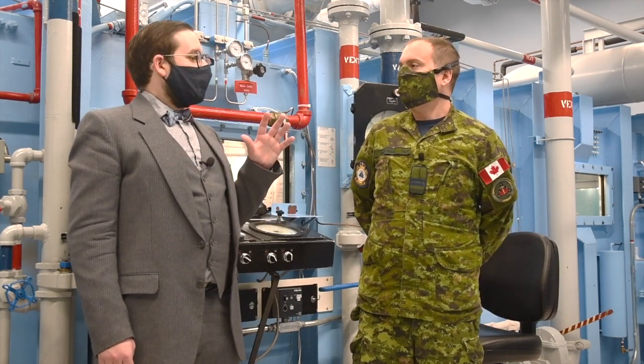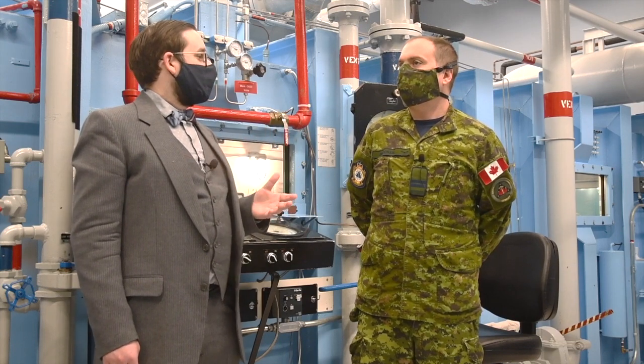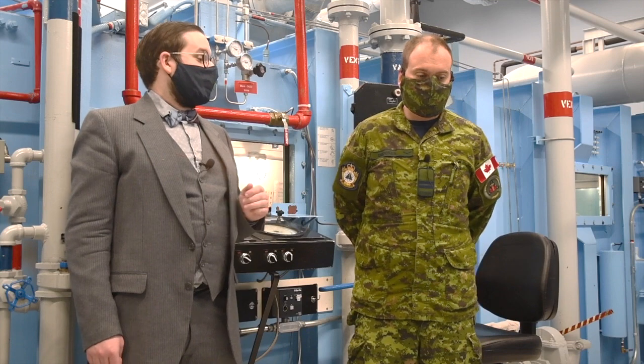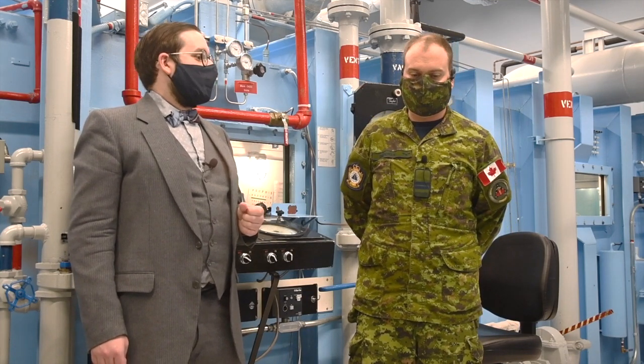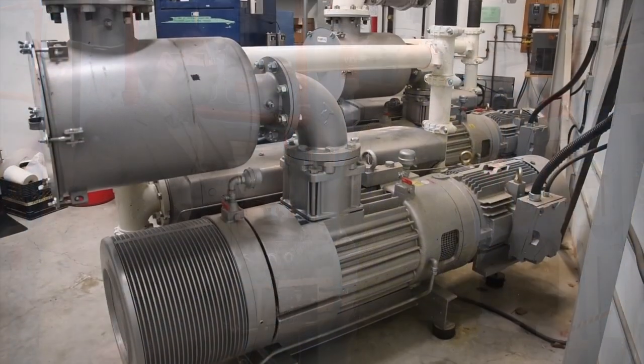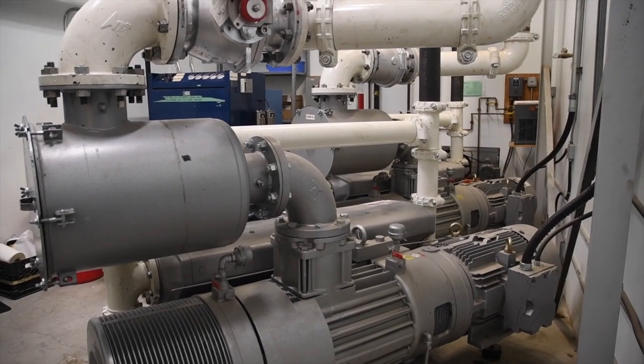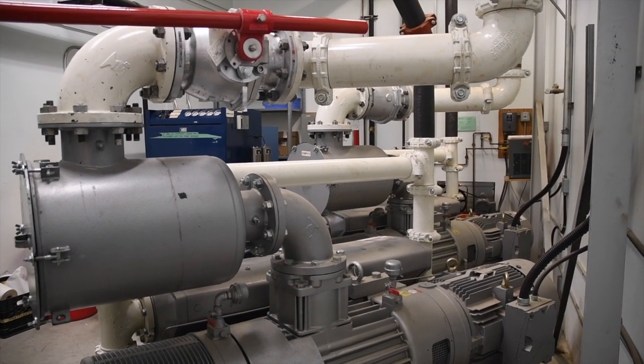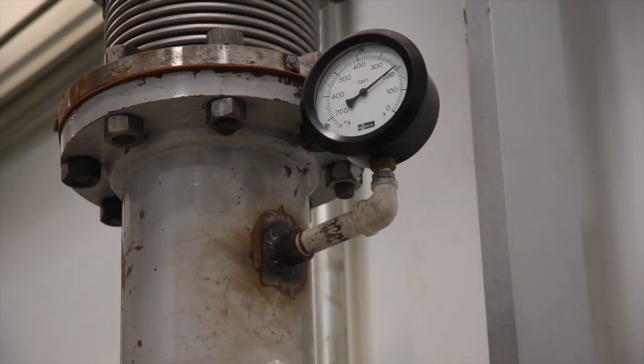How low in pressure can these chambers go? This chamber is actually rated to go to 100,000 feet. There are two vacuum pumps here that will actually do that — they're very loud and noisy, but that's exactly what they do. We have enough capacity to take the air out of the chamber to simulate about 100,000 feet if that were necessary.